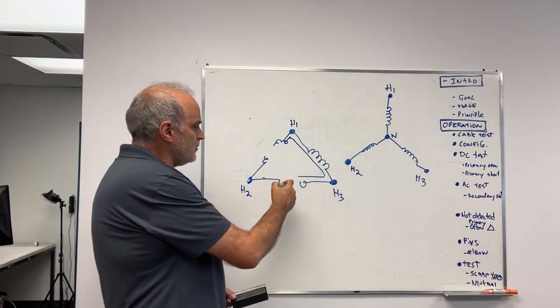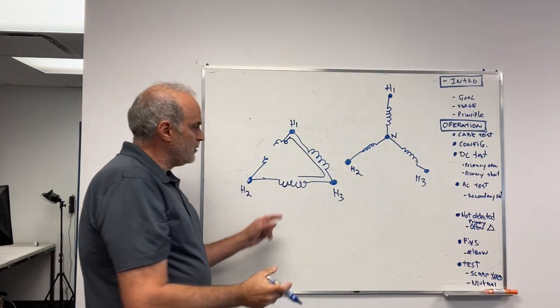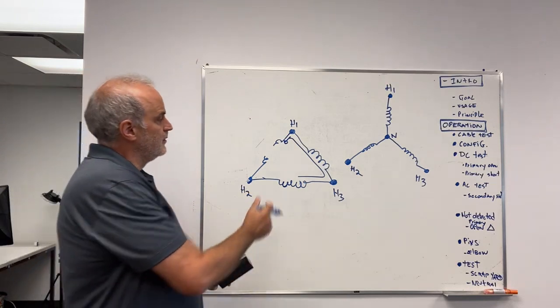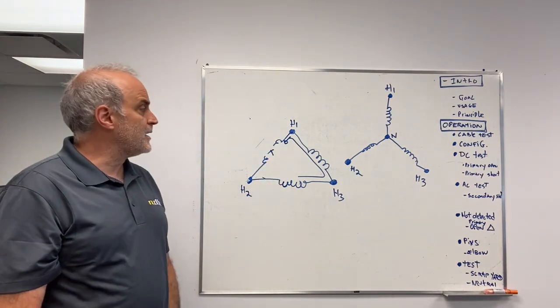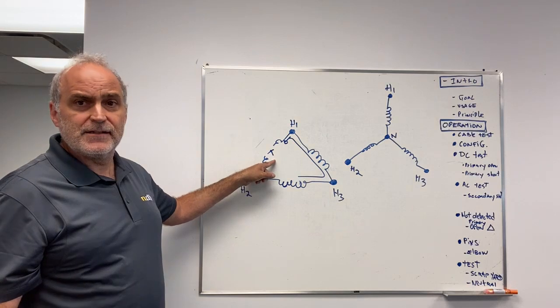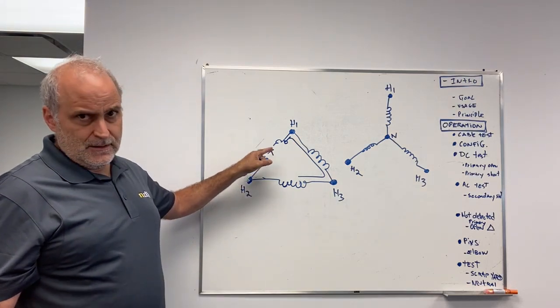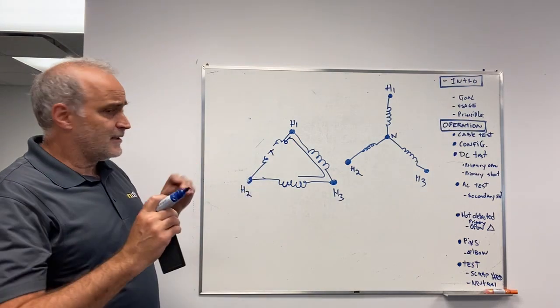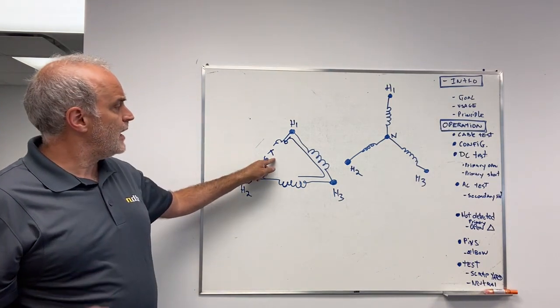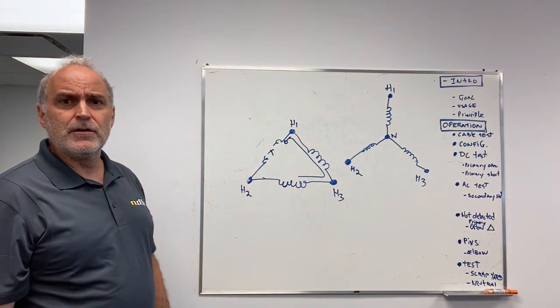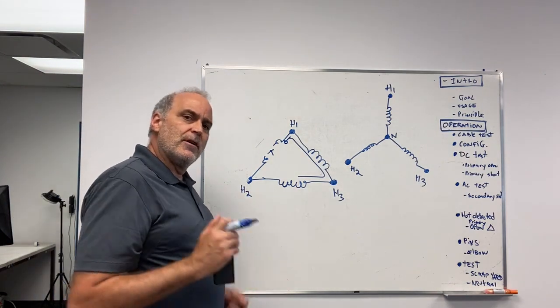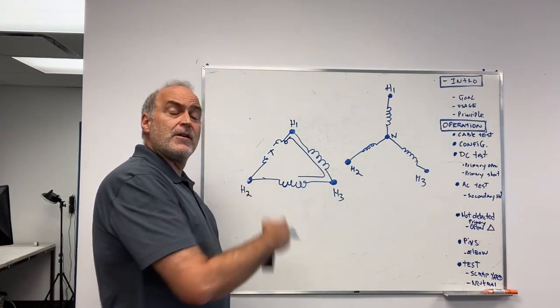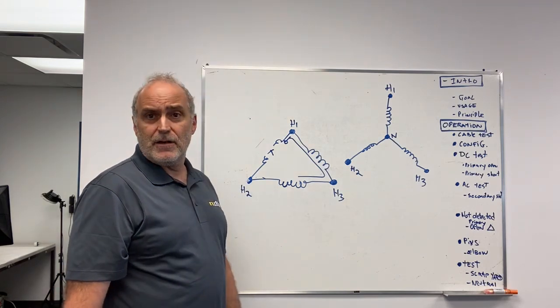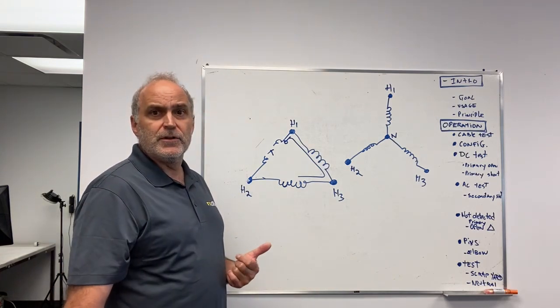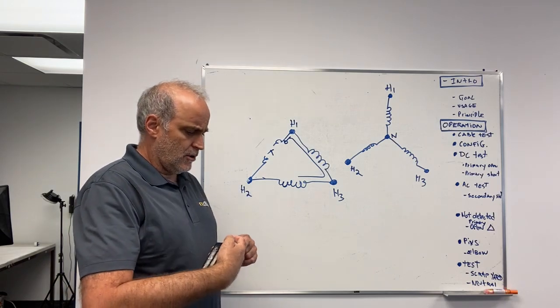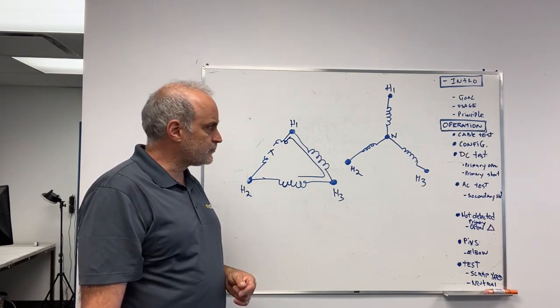But if only one winding is open on the delta, this one, I will not be able to know it. But this is not a safety issue. If one leg of your primary is open, there is no issue with the worker. If you put the fuse back on, nothing will happen. I mean, it will not work. You'll know it, but the worker or the lineman is not in danger.